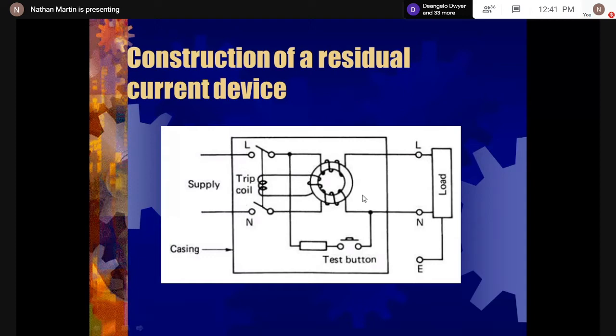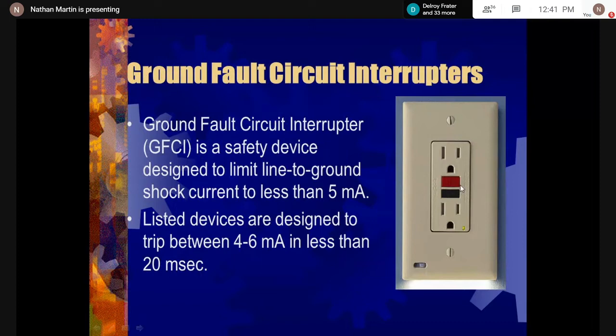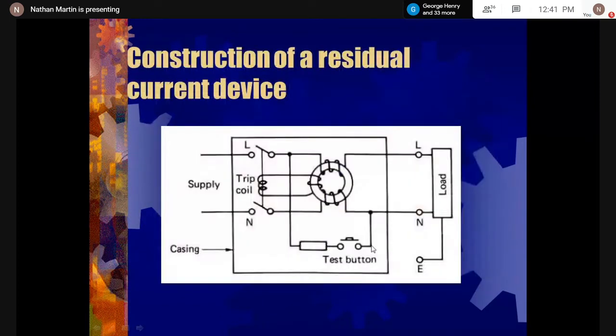Now, the test button. Looking back at the device, I have a test button. So we have the reset button and we have the test button. How the test button works is that you have a resistance here. This is put in place so as not to directly short the neutral to the live, which would create a short circuit. If you close this test button, because we develop a node here, you're going to have some current flowing here and some current flowing here. The current in this coil will be different from the current in this coil, and you will have an induced voltage in the trip winding, and hence a current will flow in the trip coil and cause the device to operate.